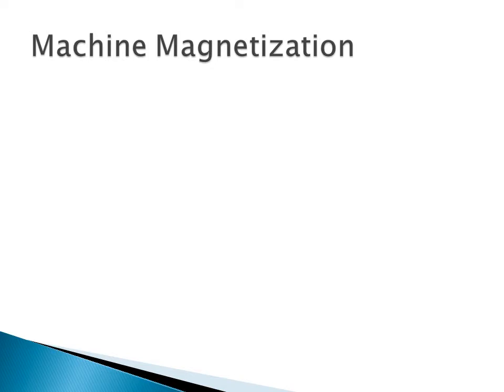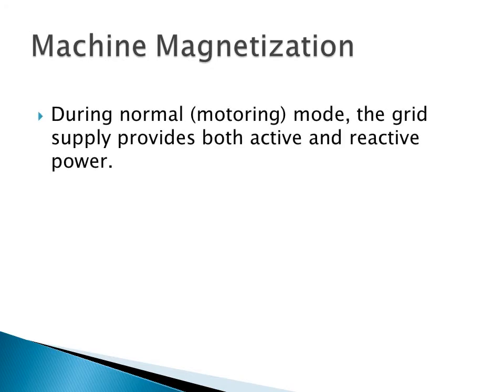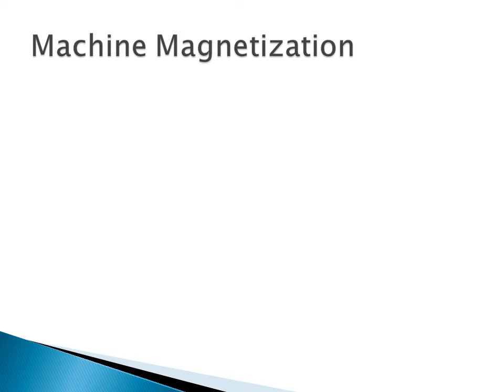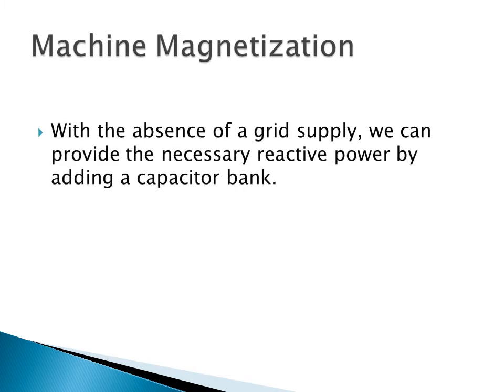During normal operation, we'd have the grid supply, which would provide both active and reactive power, where the active power is used to produce the torque, and the reactive power is used to magnetize the machine. But since we won't have a grid supply in a lot of these isolated micro hydro setups, we can provide the necessary reactive power from a bank of capacitors.